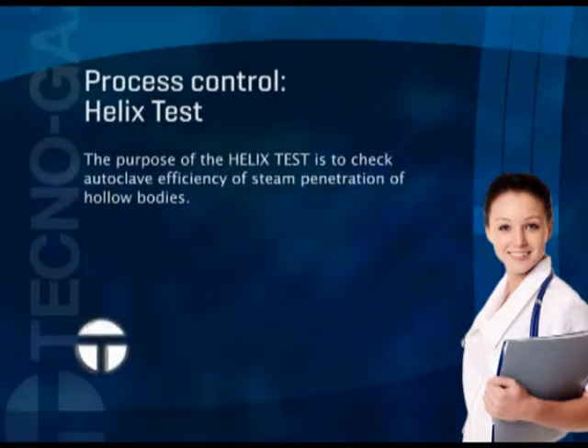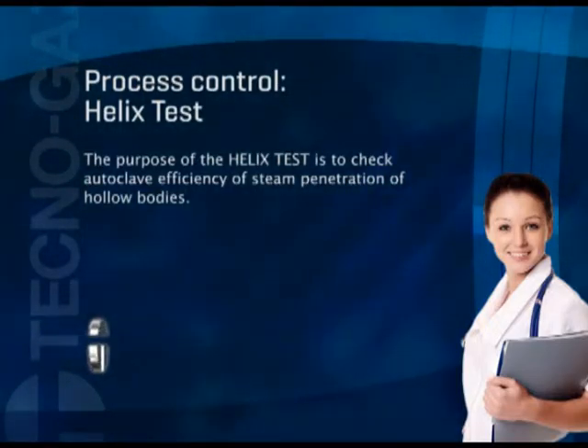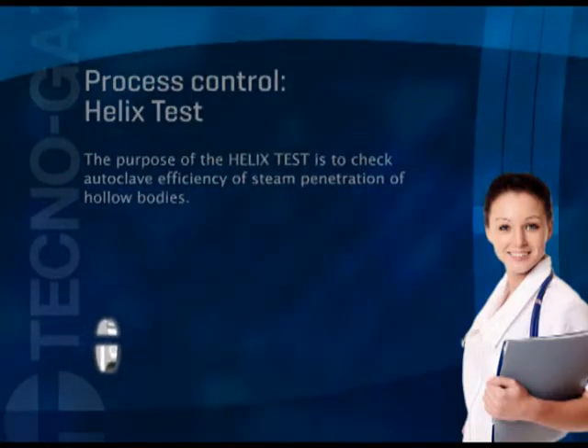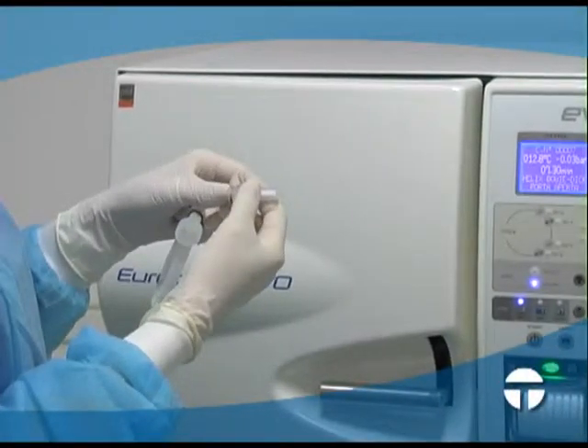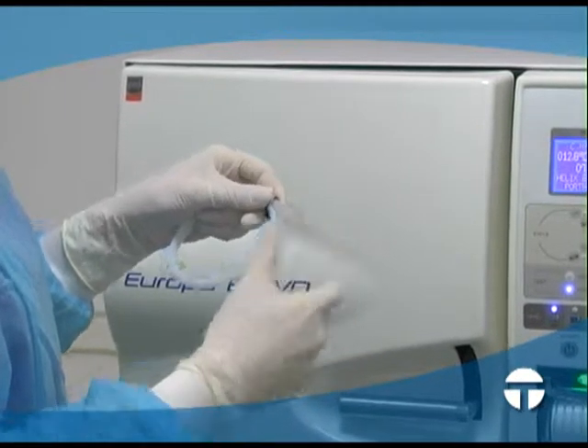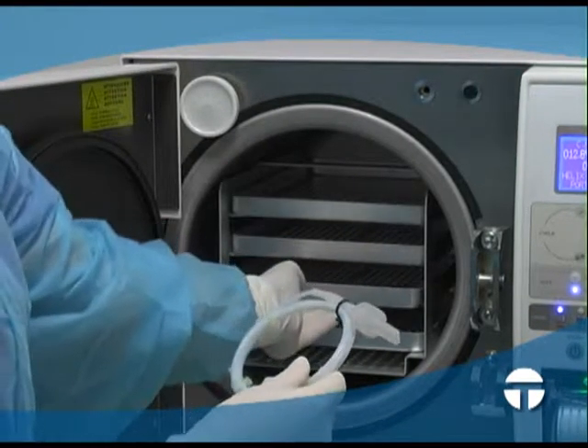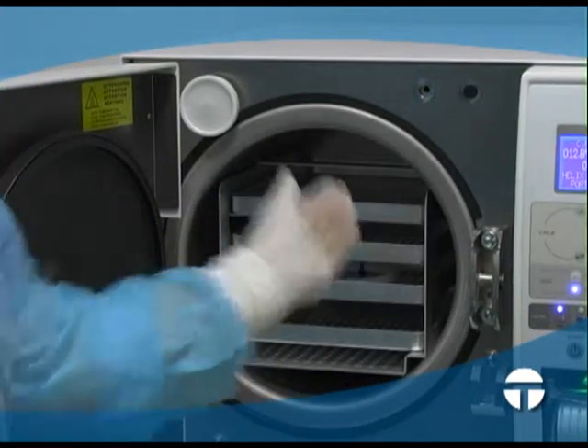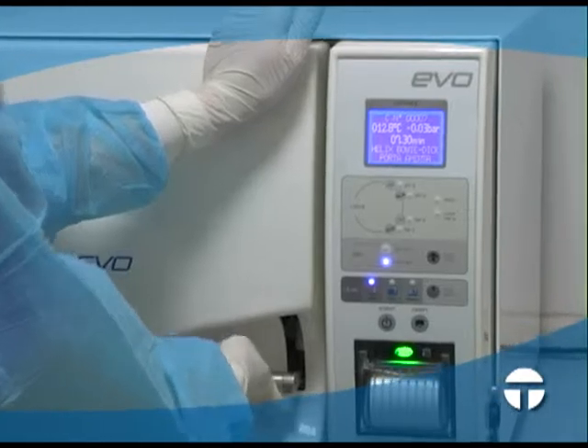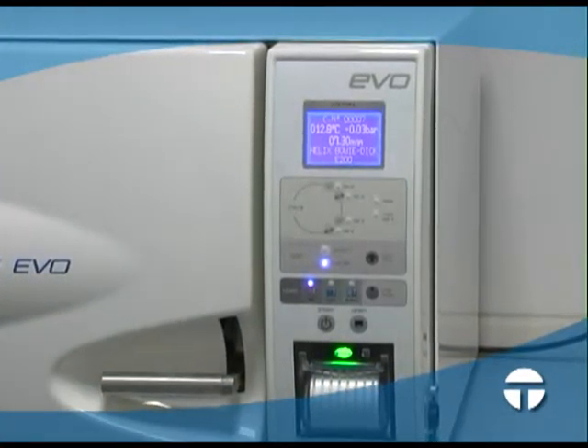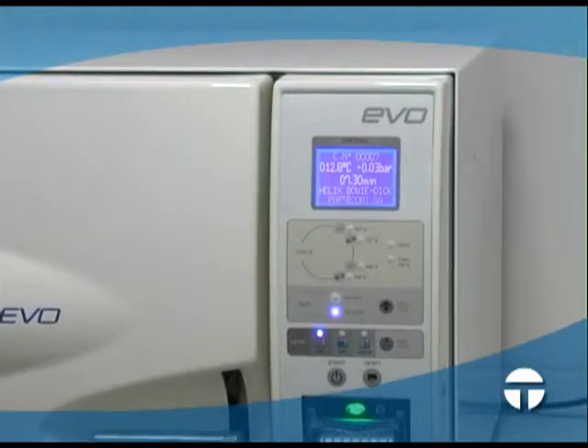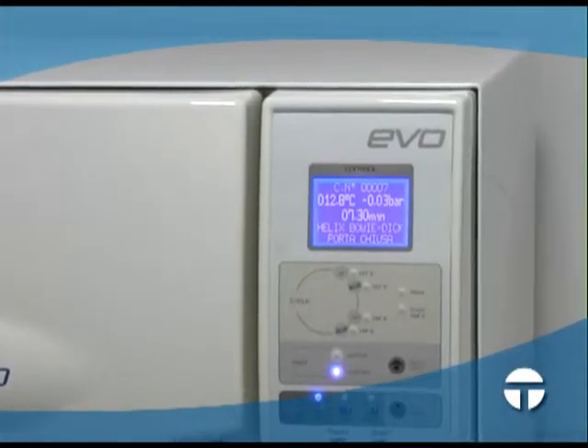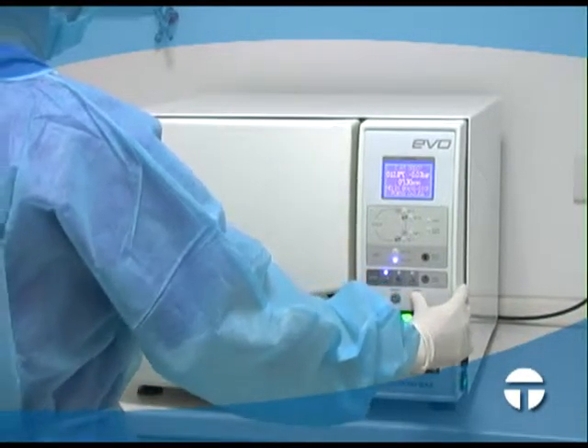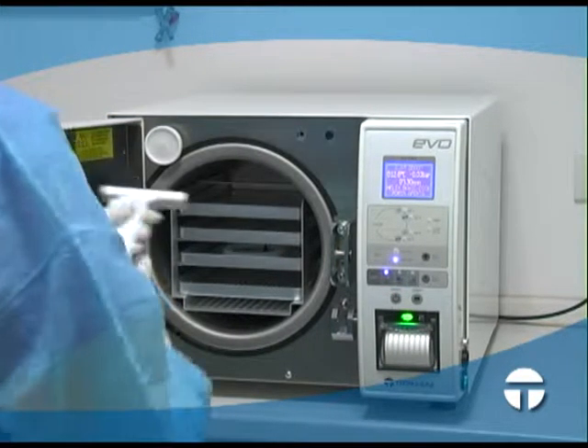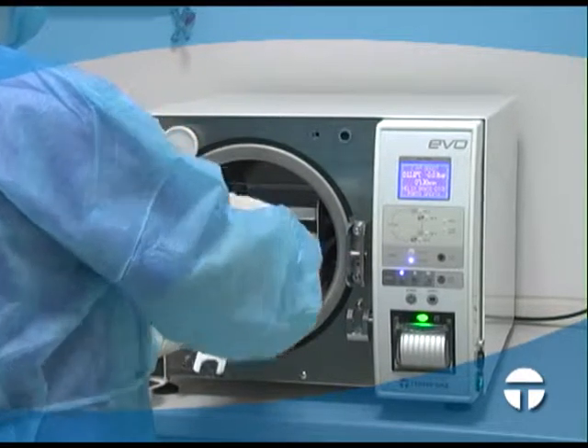Helix Test. The purpose of the Helix Test is to check autoclave efficiency of steam penetration of hollow bodies. Place the indicator in the capsule of the Helix Test system. Place the Helix Test system on the central tray of the sterilization chamber without any load. Close the door. Select the Helix Test cycle and start it. At the end of the cycle, remove the test from the chamber. Open the capsule, extract the indicator and check the result.